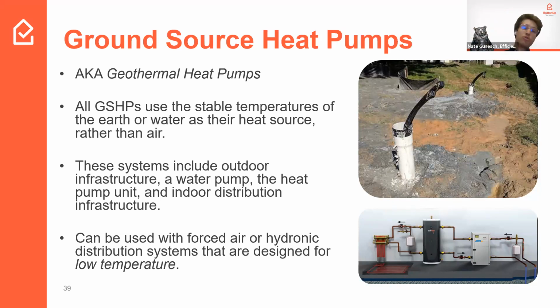The same principles of distribution apply that we've talked about so far, so you can use forced hot air or hydronic — these systems work for either, which gives people a lot of flexibility. But again, they have to be designed for low temperatures. The same principles we discussed with ducted heat pumps apply to a ducted ground source system, and the same with air-to-water heat pumps applies to hydronic distribution for a ground source heat pump. So the same rules apply: talk to a contractor and see if your existing system is usable with a ground source heat pump. That's a really worthwhile conversation to have.